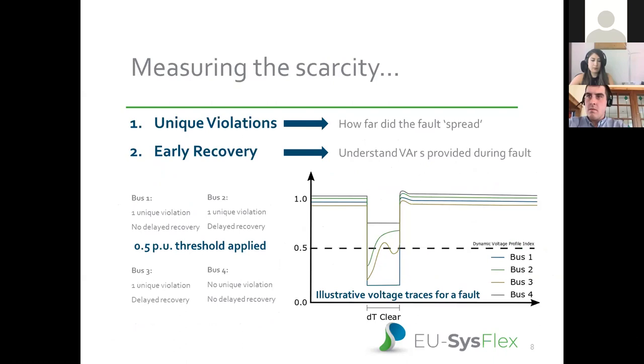So the first scarcity I want to talk about today is dynamic voltage control. And when you're performing a study of this nature, you really have to use measures of what am I trying to understand? Have a rigid way of defining, is there a problem? Is there not a problem? Measuring that. The metrics we used for this study were unique violations and early recovery, where unique violations just counts the number of buses that go below 0.5 per unit after a fault.